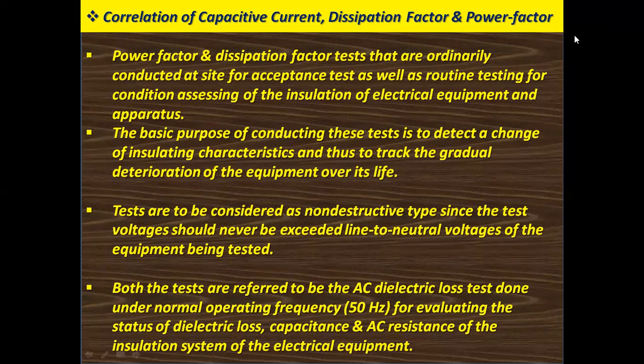Correlation of capacitive current, dissipation factor, and power factor. Power factor and dissipation factor tests are ordinarily conducted at site for acceptance tests as well as routine testing for condition assessment of the insulation of electrical equipment and apparatus. The basic purpose of these tests is to detect a change of insulating characteristics and thus to track the gradual deterioration of the equipment over its life.